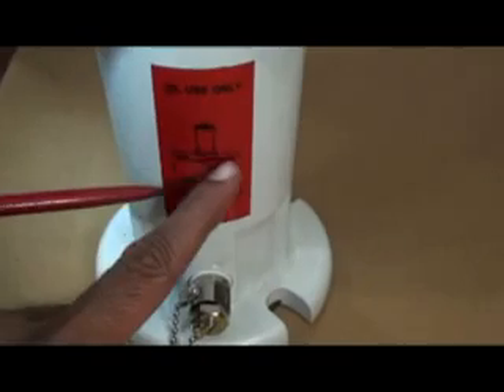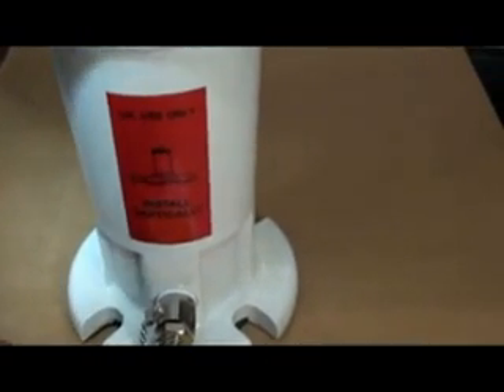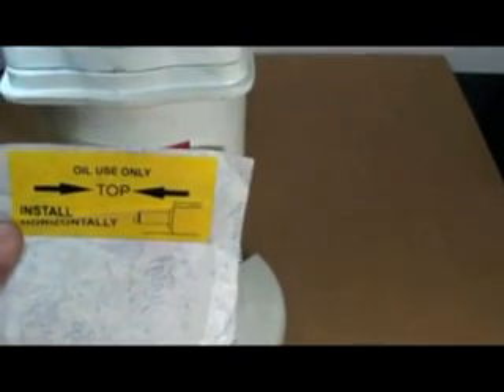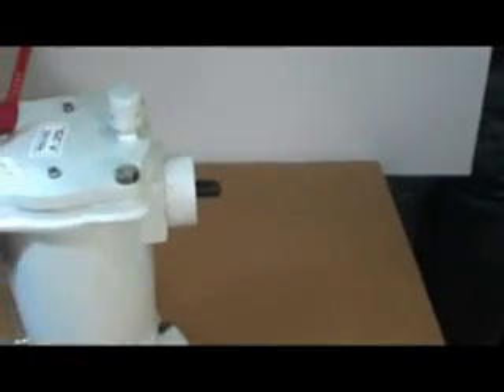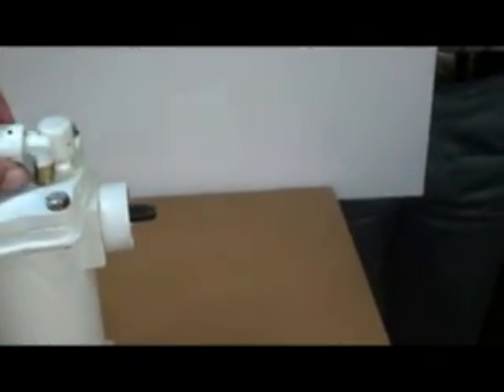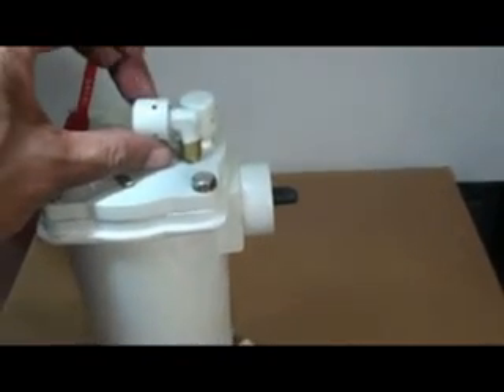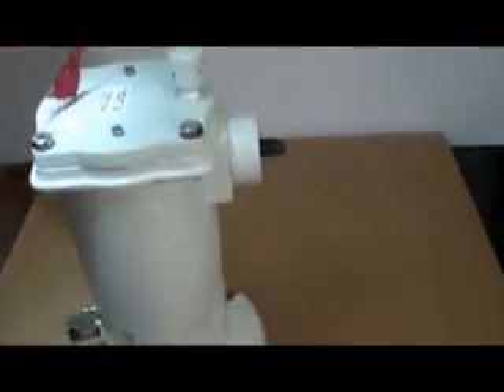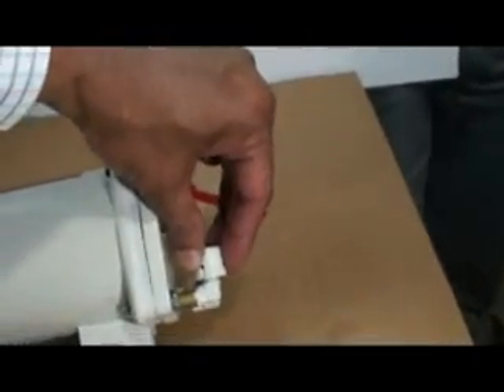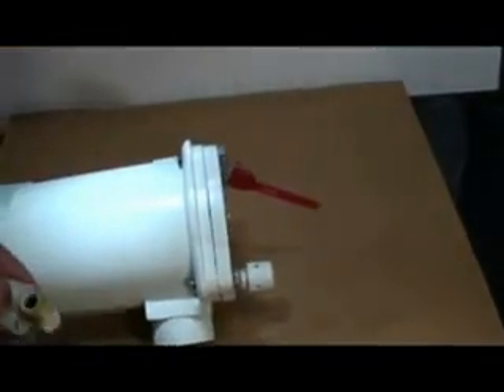Here it is a vertical type RPR. It will be mounted on the transformer tank in vertical position. You can see the other one is a horizontal type, and it will be mounted as displayed on the direction plate. And the cap will be fitted horizontally like this. So to recognize, for horizontal the cap will be horizontal, and for vertical the cap will be vertical. It is a vertical mounting air plug.